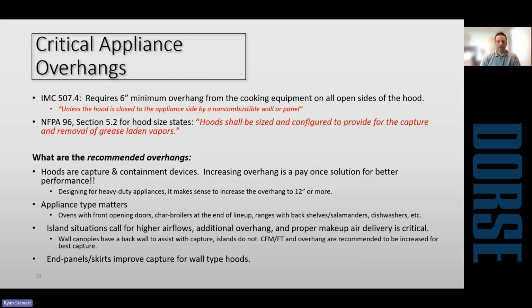So overhang, that's one of the things as airflows have been pushed down by energy codes. International Mechanical Code, as long as I can remember, has always said 6-inch minimum overhang on all open sides. And I think the exception to that is if you have a wall or some sort of a containment panel, then you can get reduced overhang.